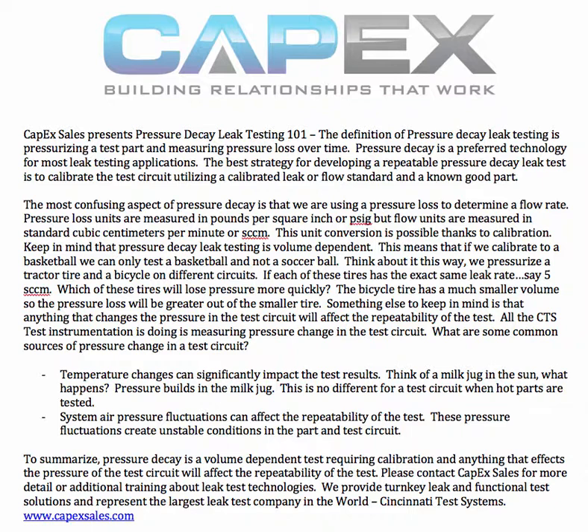So in other words, if you change out a test line because it's broken or whatever, and you change it from 2 foot to 3 foot, then you need to recalibrate. Anytime you have a potential effect on the volume of your part, you will need to recalibrate your system.